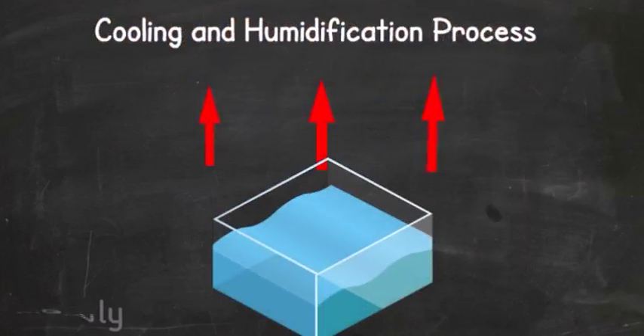In this process, the moisture is added to the air by passing it over the stream or spray of water which is at a temperature lower than the dry bulb temperature of the air. When the ordinary air passes over the stream of water, the particles of water present within the stream tend to get evaporated by giving up the heat to the stream. The evaporated water is absorbed by the air so its moisture content, thus the humidity, increases.